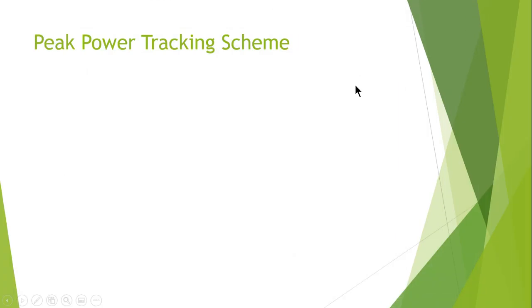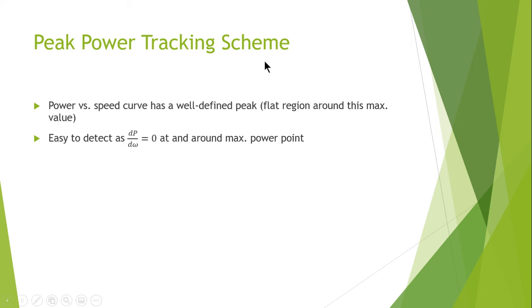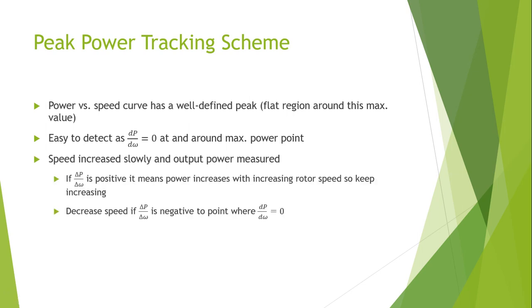The next scheme is the peak power tracking scheme. The peak power versus speed curve has a well-defined peak with a flat region around the maximum value, which is easily detectable using the first derivative of power with respect to speed equals zero at the maximum power point. The rotor speed increases slowly and the output power is measured.